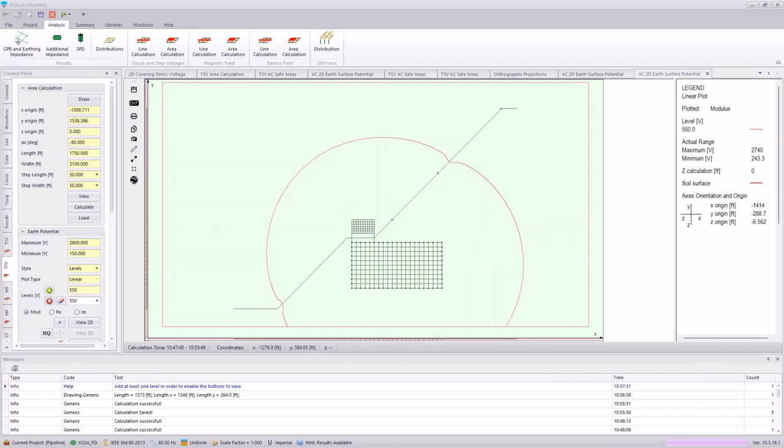I'm just going down the next question down the line here. One question is, how often do you see these analyses including additional items of current discharging into the earth in the model that will cause the Earth's surface potential to rise at these locations? Items such as connected transmission lines, pipelines, towers. So essentially the question is asking, how detailed do we get with these models? Really, you want to get as detailed as you can.